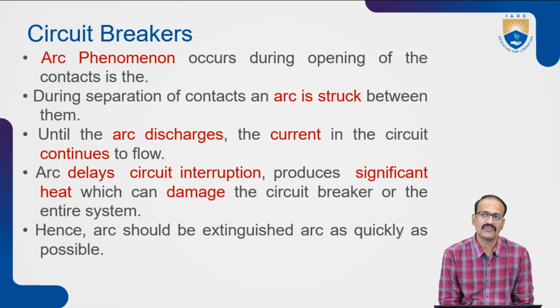Here the main problem with the circuit breaker is a phenomenon called the arc phenomenon. We are placing the circuit breaker for power system protection, and it will open the contacts. Under normal conditions, they will be closed and the current will be passing. The circuit will be functioning and is not broken. Under abnormal conditions, the trip coil gets energized and the electrodes will move away to break the passage of the electricity.